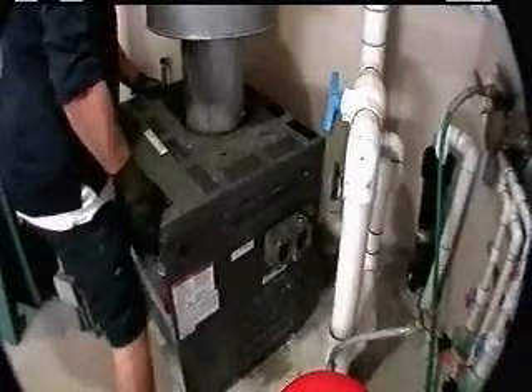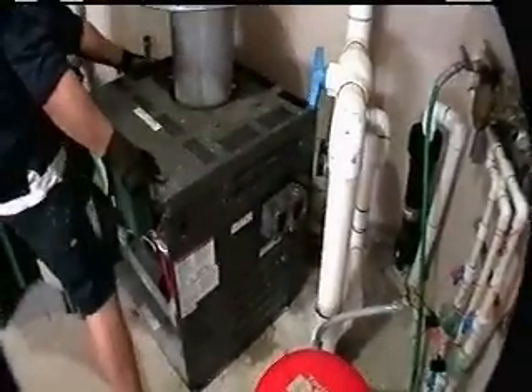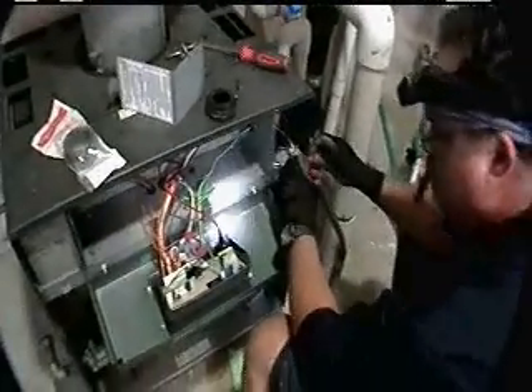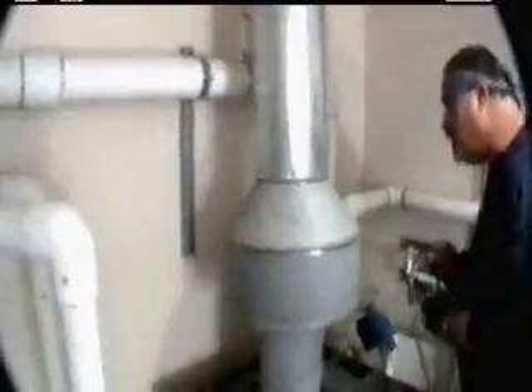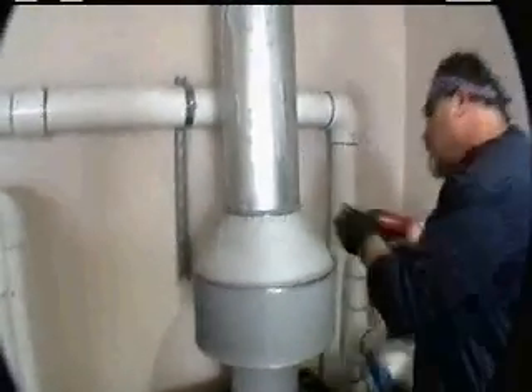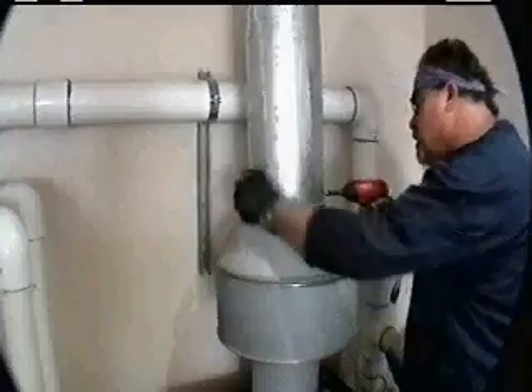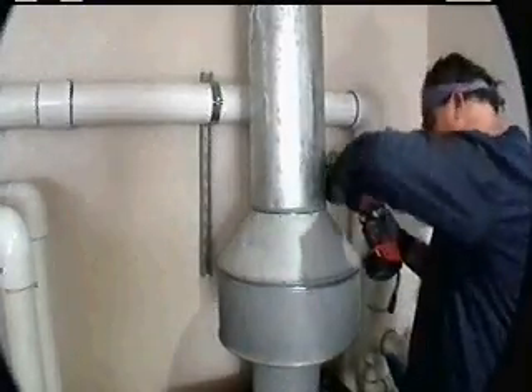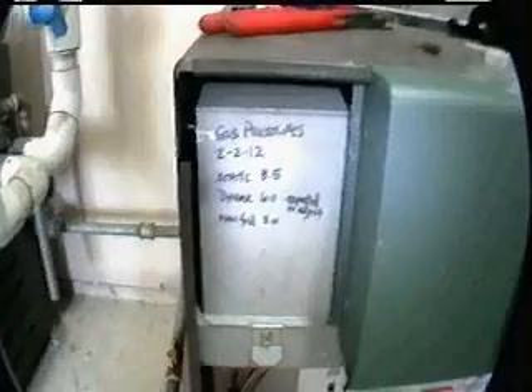See, the heat exchanger is back on. This is about a 300-pound heater, but you can manage to scooch them around, you know, not too bad. So he'll very gently move it back into place. Once he gets it all lined up, he can rebolt it back on, reconnect the electrical, reconnect the vent stack, reconnect the gas, and double check to make sure everything is lined up properly.